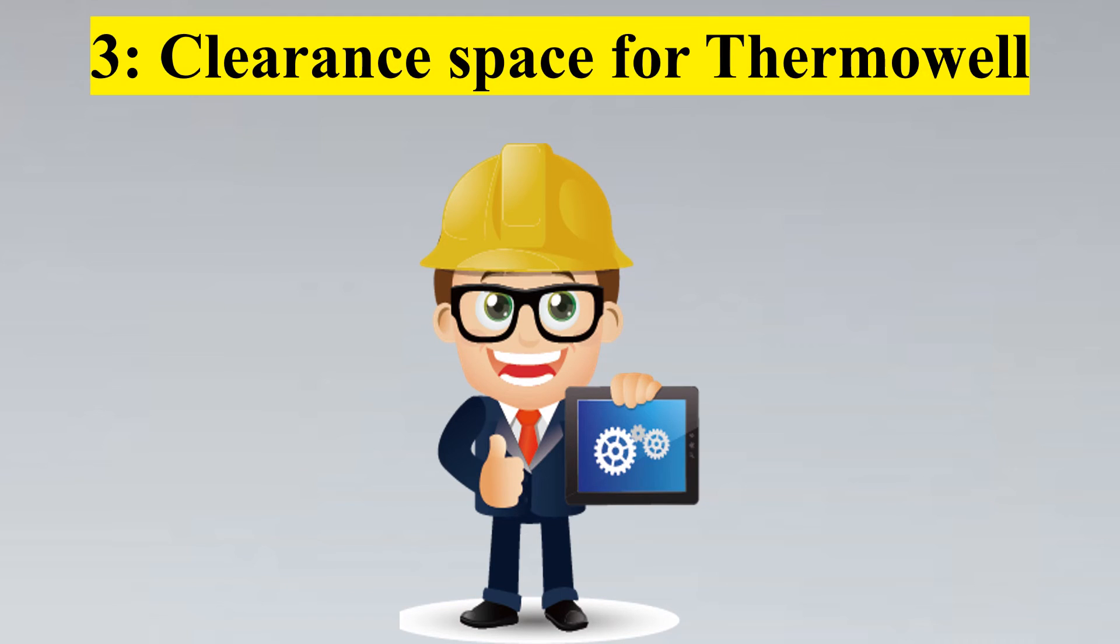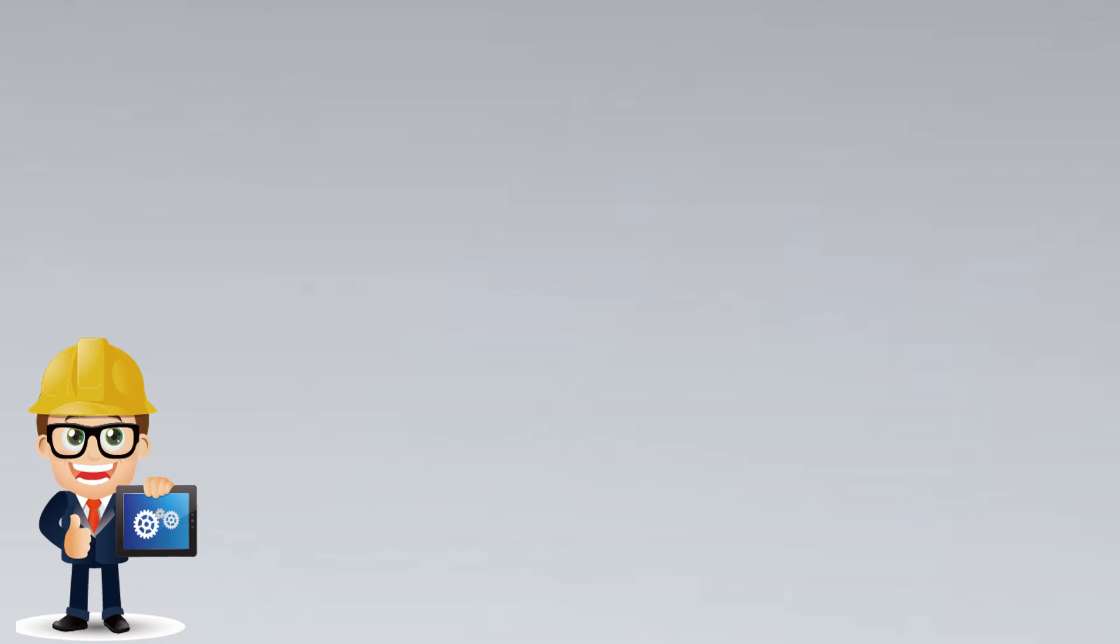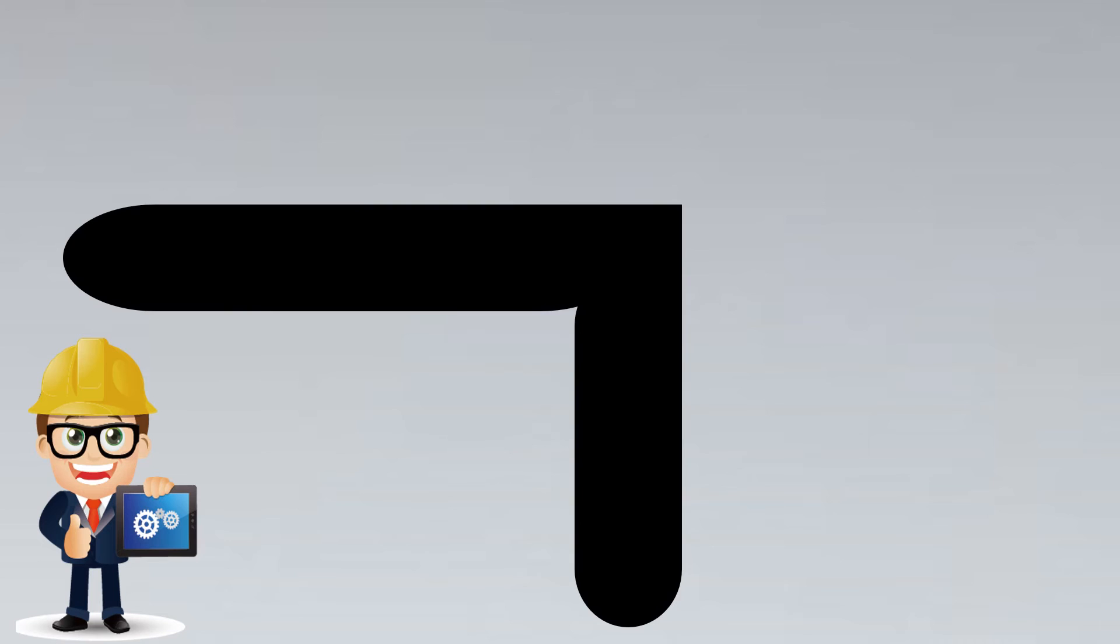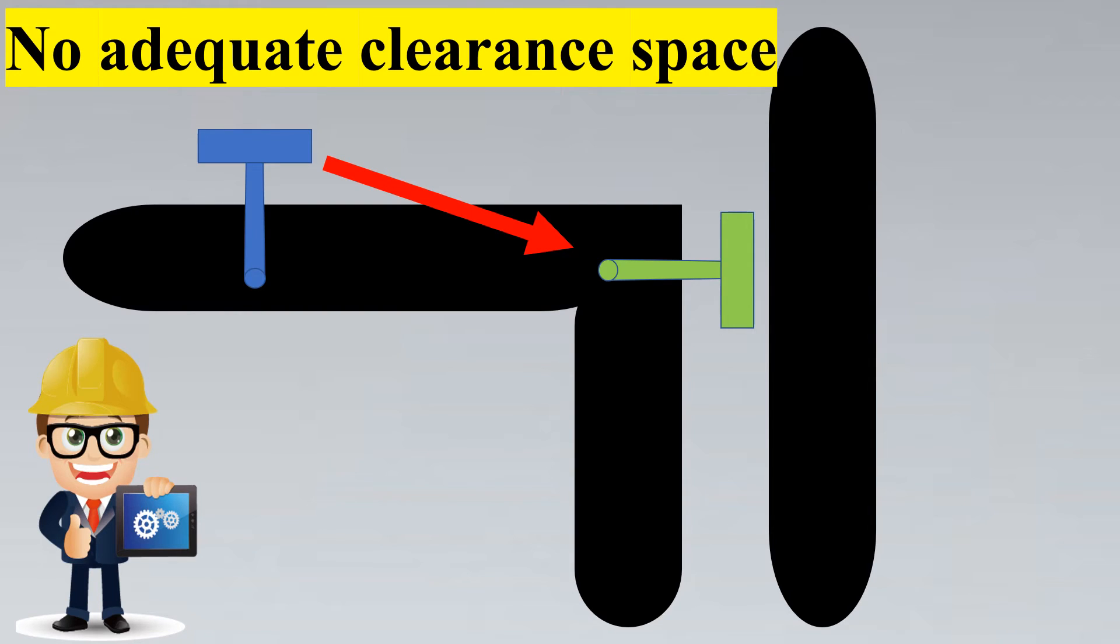Now let's look into the next criteria which is the clearance space for thermowells. What does this criteria state? This criteria is an easy criteria but often gets forgotten. And this is that imagine that this is your elbow and you have to install your thermowell from here to here which is the elbow as we stated. It seems to be simple right? But what if there is a pipe nearby to it? How would you remove the thermowell from the process? This seems to be a confusing issue. And if you notice that in such cases there is no clearance space provided and for the operations team it will be extremely difficult and thus this is not a good engineering practice.